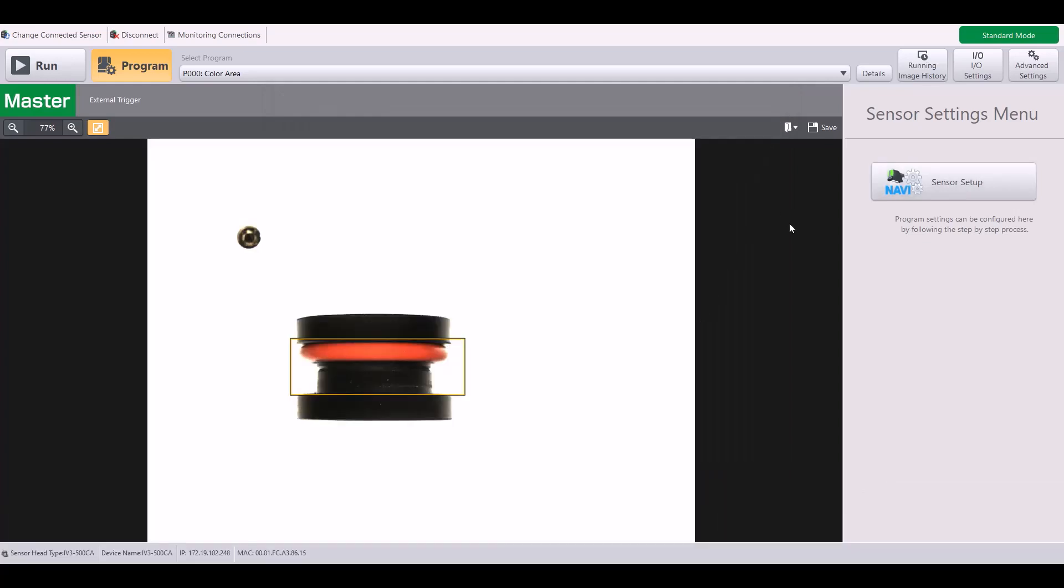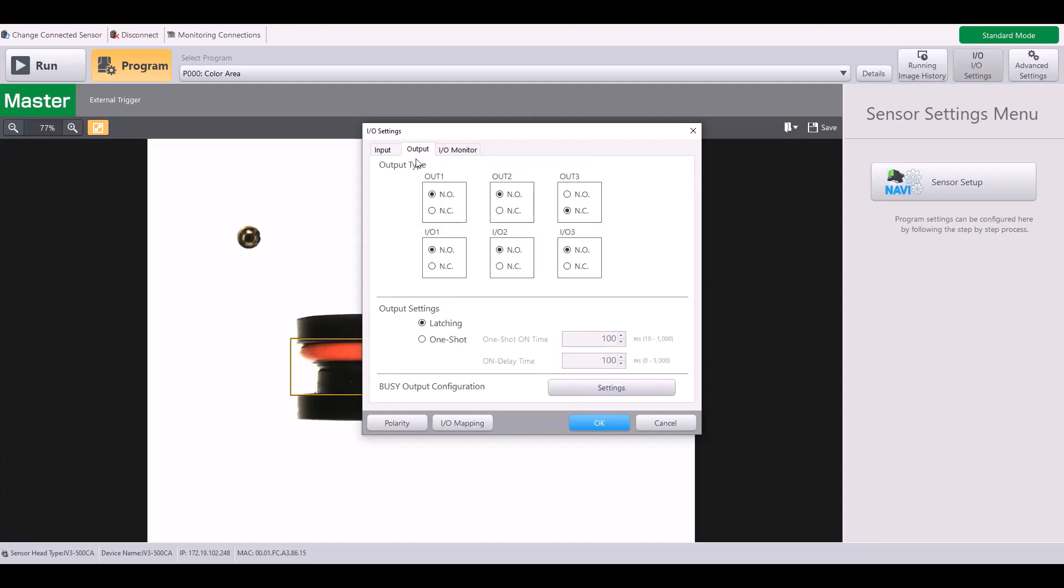The last thing I want to quickly show you is in the IO settings, if you go to your output tab, here's where you can choose from normally open or normally closed for each output that you have. And you can also enable a one-shot output versus latching. By default, the IV-3 will be latching, meaning it will hold on that judgment until the next judgment is complete.